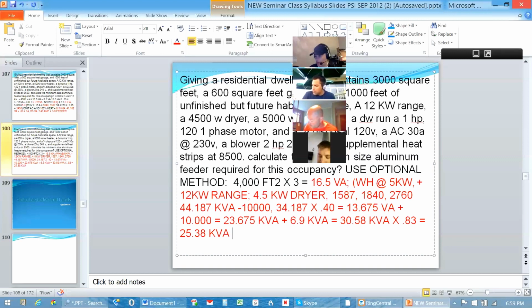And I divide that by 240 volts. Gives me 105.74 amps. So since I'm using a kVA value, I divide that by 0.240. If you're doing it in volt-amps, just divide it by 240. Gives me 105.74 amps. So the aluminum feeder for this one, again, the same procedure applies. I'm going to be looking at the 75-degree column. I end up with a 1-aught instead of a 3-aught aluminum feeder for that service, even an option.